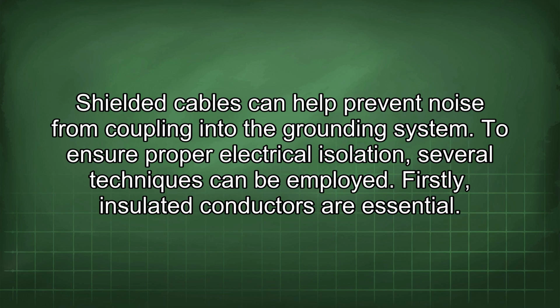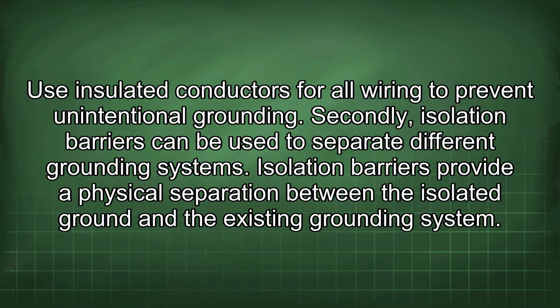To ensure proper electrical isolation, several techniques can be employed. Firstly, insulated conductors are essential. Use insulated conductors for all wiring to prevent unintentional grounding. Secondly, isolation barriers can be used to separate different grounding systems. Isolation barriers provide a physical separation between the isolated ground and the existing grounding system.